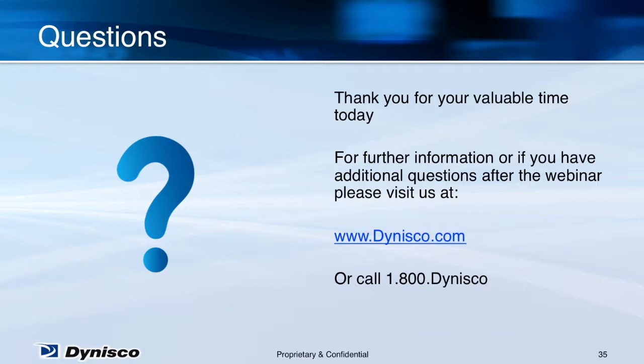How many tests should I do on my melt flow indexer to obtain an accurate correlation factor for temperature variations? In the presentation, we fit the data to a line, so in theory, only 2 points are required. We would recommend an average melt flow index be determined over multiple tests at at least 2 different temperatures. I would recommend doing more than 2, though, so you can check the accuracy of the fit.